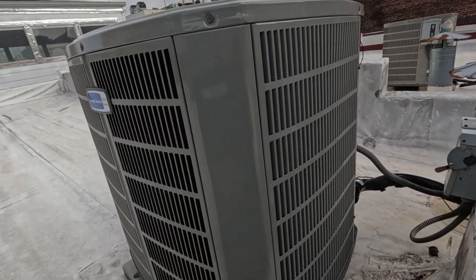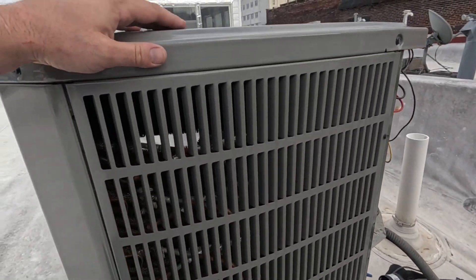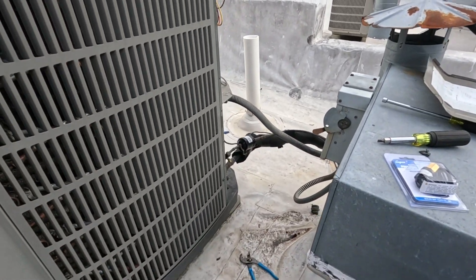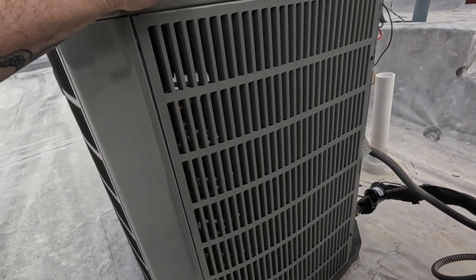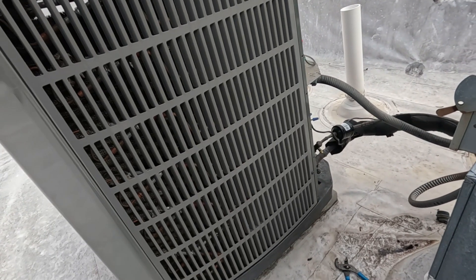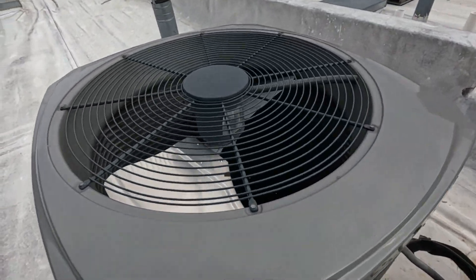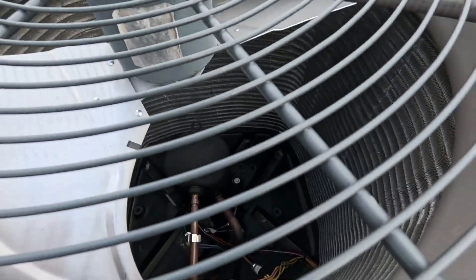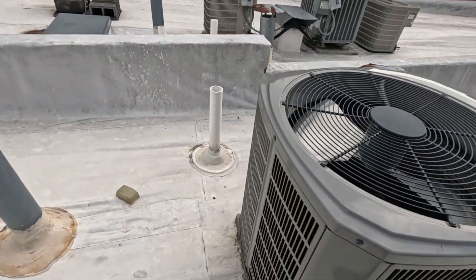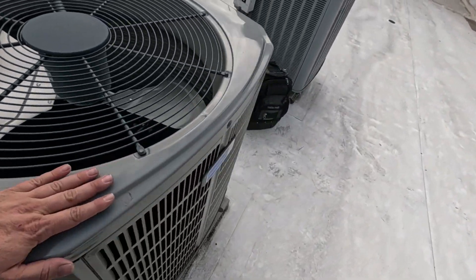So this is the condenser - it's a Trane. Like I said earlier, it's in the 60s today and has been all week. This is just a straight air conditioner and it doesn't have any fan cycling or low ambient protection, so what I'm thinking is that it just ran too long and maybe froze up or went off on low pressure.